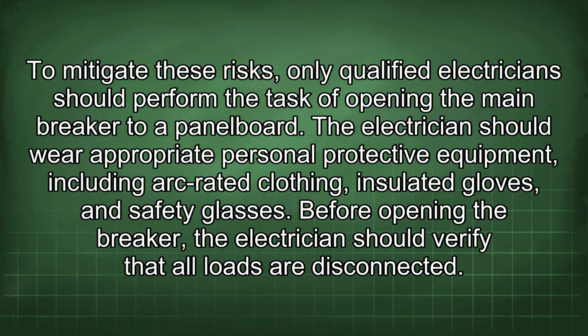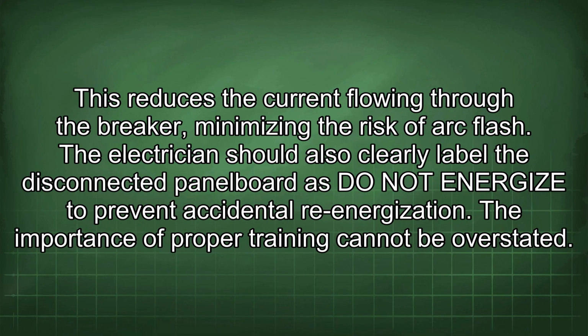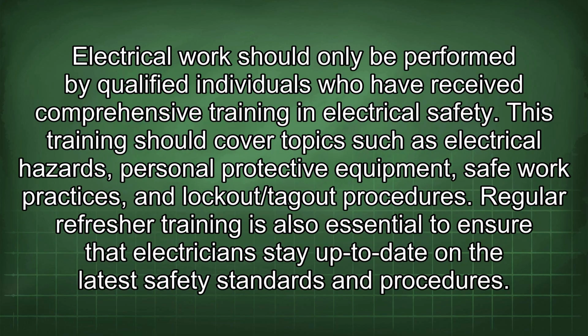Before opening the breaker, the electrician should verify that all loads are disconnected. This reduces the current flowing through the breaker, minimizing the risk of arc flash. The electrician should also clearly label the disconnected panel board as "Do not energize" to prevent accidental re-energization. The importance of proper training cannot be overstated. Electrical work should only be performed by qualified individuals who have received comprehensive training in electrical safety.